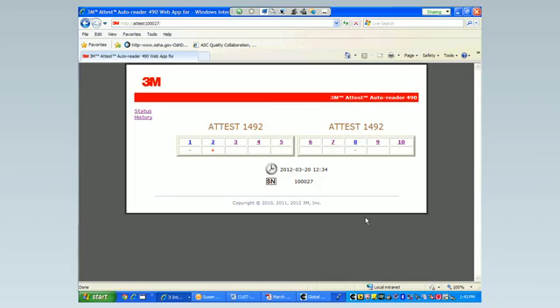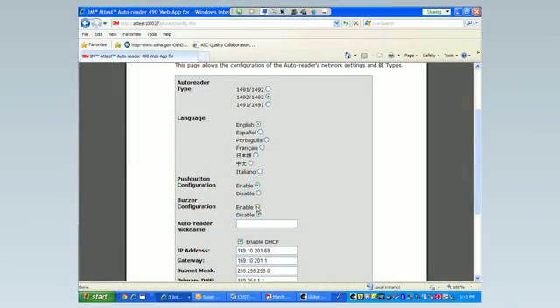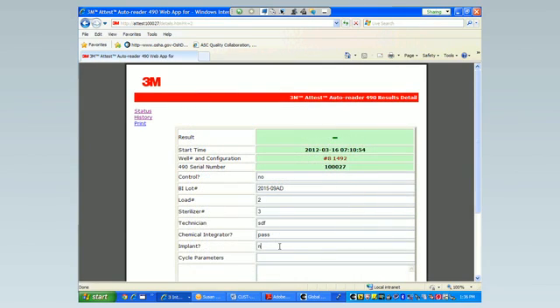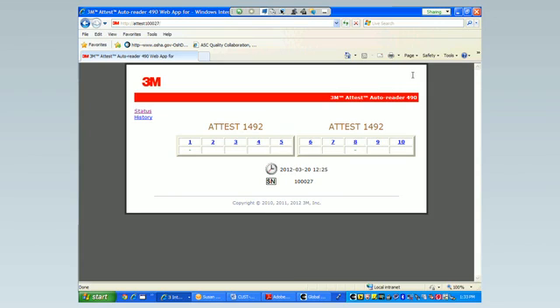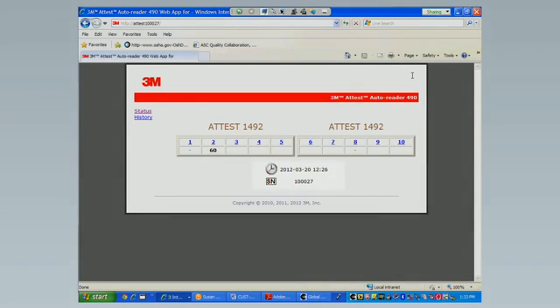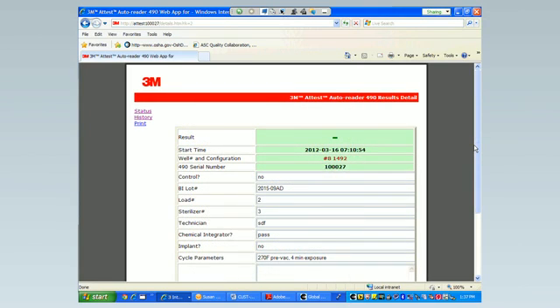The 3M Attest Autoreader 490 offers additional functionality online. Once you connect to the Attest web app, you can remotely view the current status of incubating BIs using a computer or smartphone. The web app also allows you to remotely view and configure Attest Autoreader 490 settings, view results for the last 100 BI tests, save records for your electronic files, and print records for your paper files. To connect to the Attest web app, follow the step-by-step instructions in the Attest Autoreader 490 Operators Manual. Once connected on your computer or smartphone, you'll see the status page, which provides a real-time view of the Attest Autoreader 490 configuration and LCD panel display. The current date and time and Autoreader 490 serial number are also displayed. From here, you can navigate to a history page showing the results of the last 100 BI incubations, and results detail pages by clicking on the well number of an occupied well.